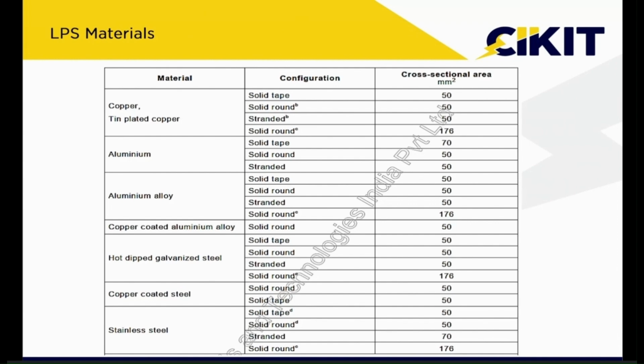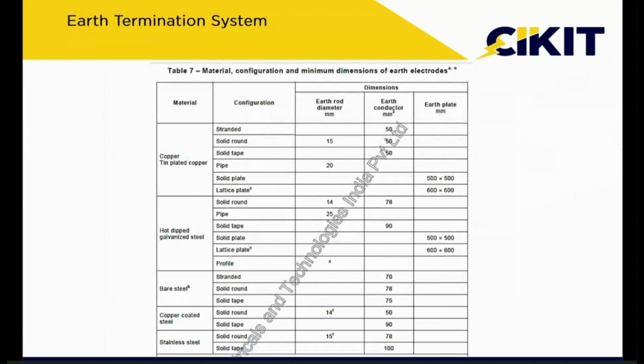So when we are using any specific material in any specific configuration for any specific condition, we need to ensure that we are matching the minimum cross-sectional requirement as per this particular standard. So this is for earthing material. Here also you can observe that we can use different materials, but they have removed aluminum because aluminum, even though it's a very good conductor, should not be used below the soil because it corrodes much faster. Here also they have provided different configurations. We can use rod, pipe, or earthing conductor in the form of strips or plate. So when we are using a rod configuration of any specific material, we need to ensure that we are matching the diameter provided by this particular standard recommendation.